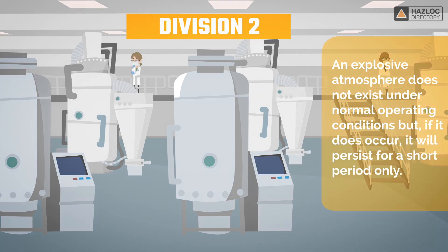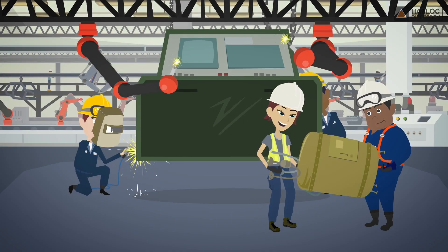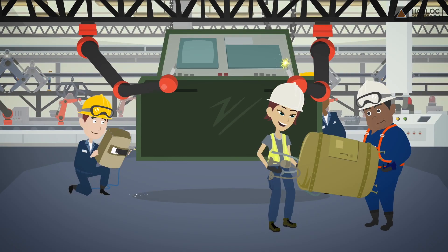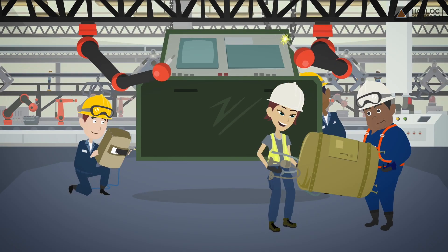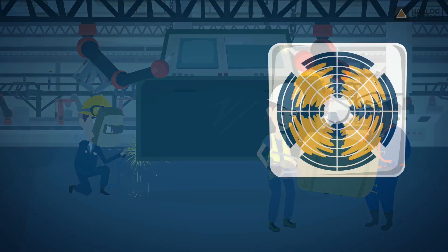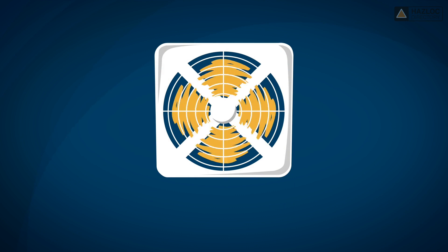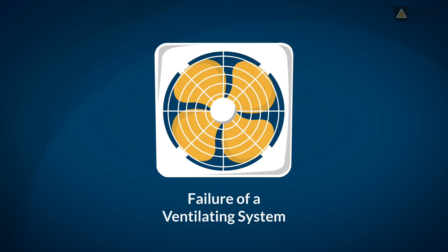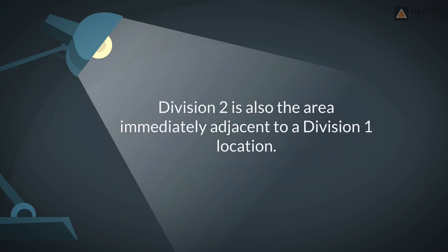A Division 2 area might be created during repair or maintenance activities, accidental rupture of a vessel or container, or failure of a ventilating system. Division 2 is also the area immediately adjacent to a Division 1 location.